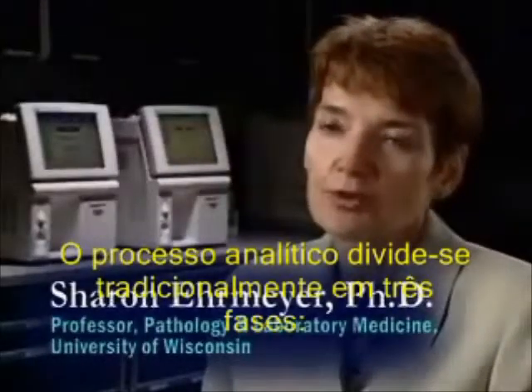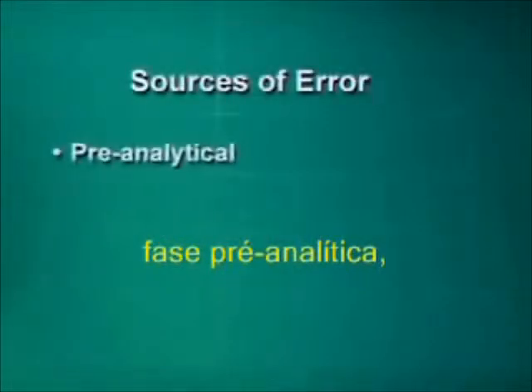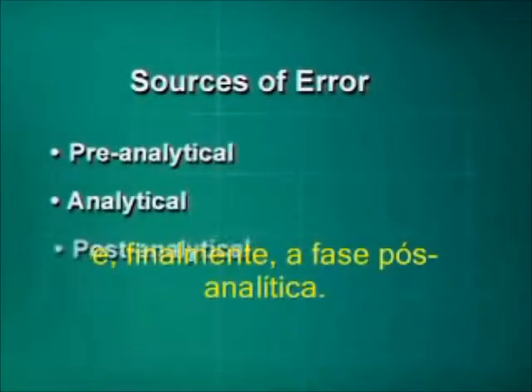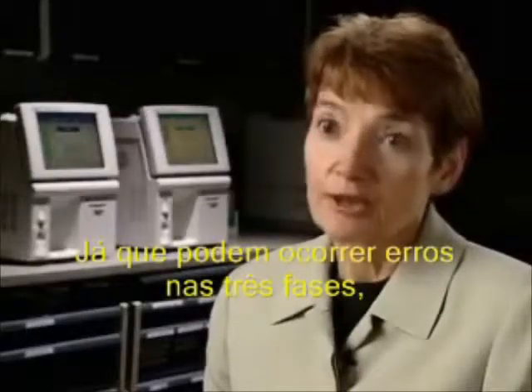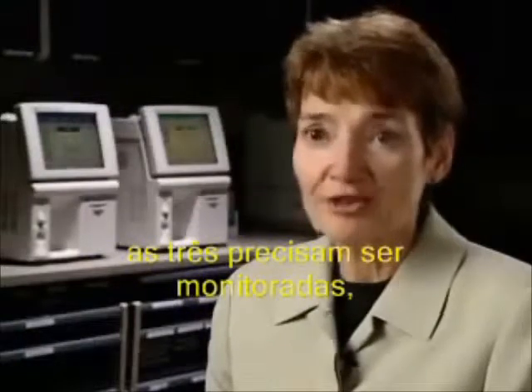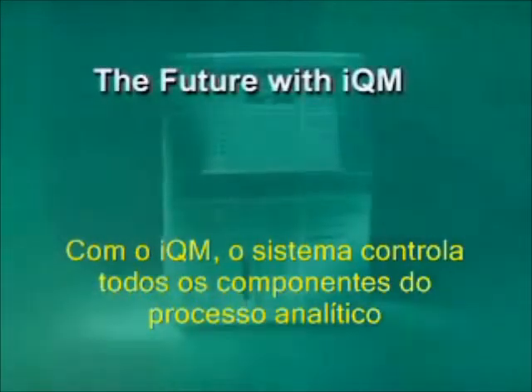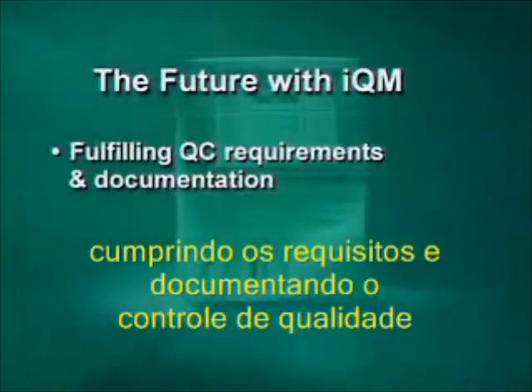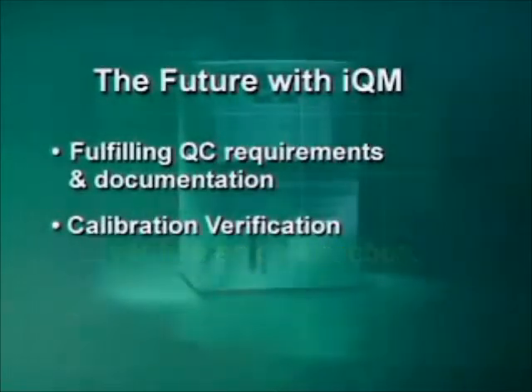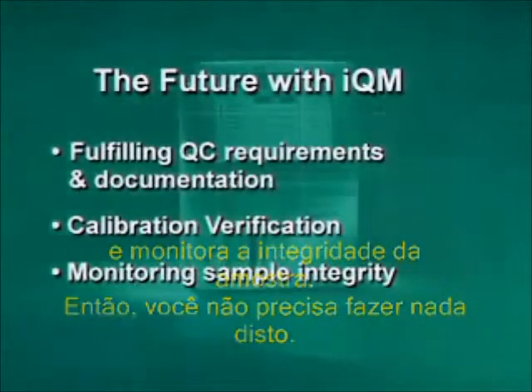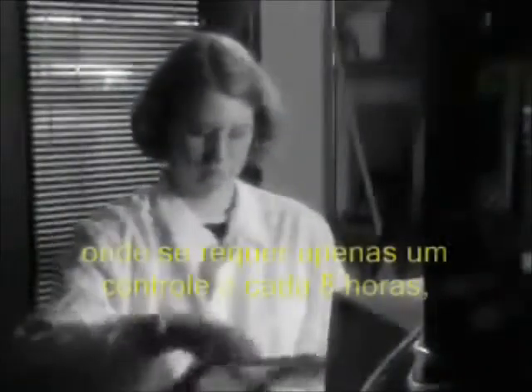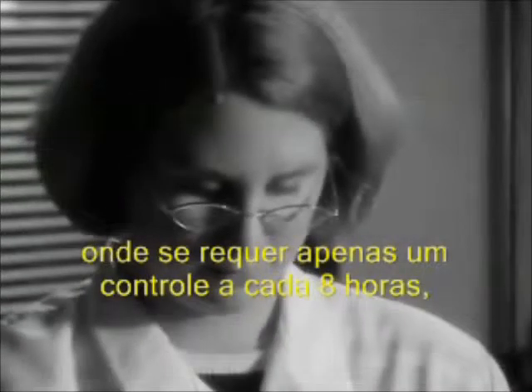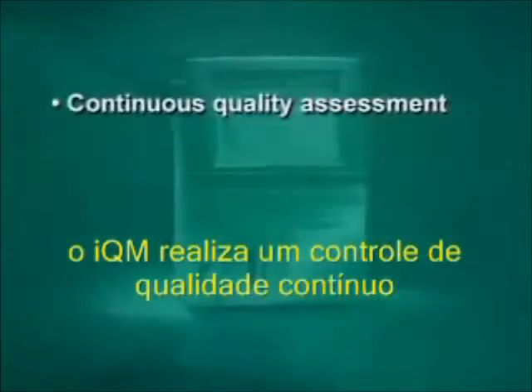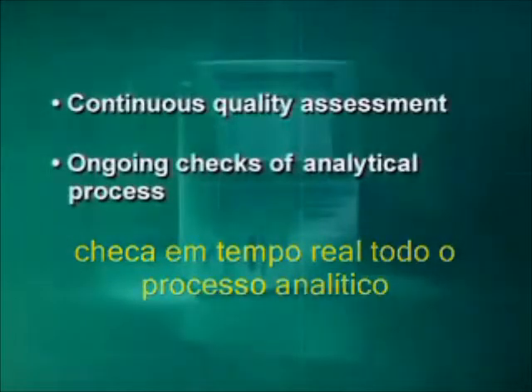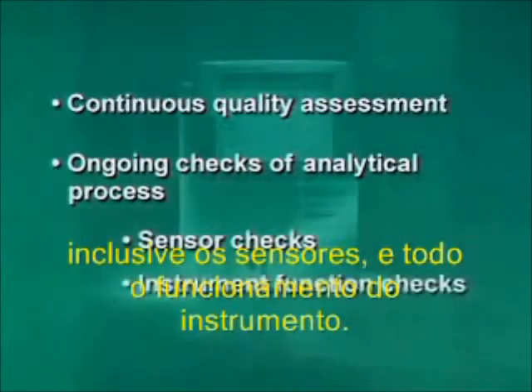The testing process is traditionally broken down into 3 phases. This includes the pre-analytical phase, the analytical phase, and finally the post-analytical phase. Since errors can be generated in all 3 phases, they need to be monitored and safeguards need to be built in. With IQM, the system tracks all components of analytical testing, including QC requirements and documentation, calibration verification, and monitoring sample integrity, so you don't have to. And unlike traditional QC, where minimum regulatory requirements set QC checks every 8 hours, IQM conducts continuous quality assessment and ongoing checks of the analytical process, including sensor and instrument function checks.